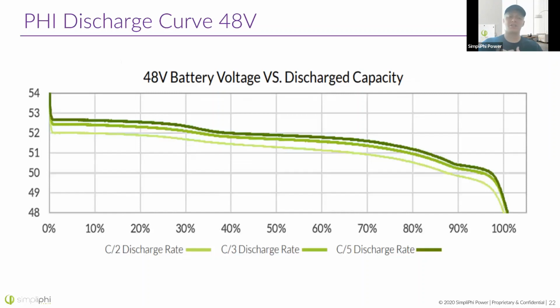This is a much better demonstration here. It just shows you how flat this curve is, right? So between 52 volts and 51 volts, a 1 volt drop equates to about 70% state of charge difference. Man, on a lead acid battery, that'd be more like 4 to 6 volts for a 70% state of charge difference. So having only a 1 volt window makes your voltage reading not tell you all that much about the battery state of charge.